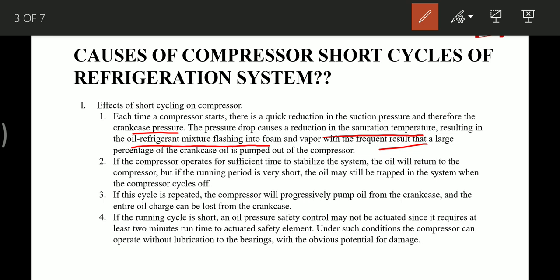If the compressor operates for sufficient time to stabilize the system, the oil will be returned back into the compressor. But if the running period is very short, the oil may still be trapped in the system when the compressor is switched off or the cycle is switched off.